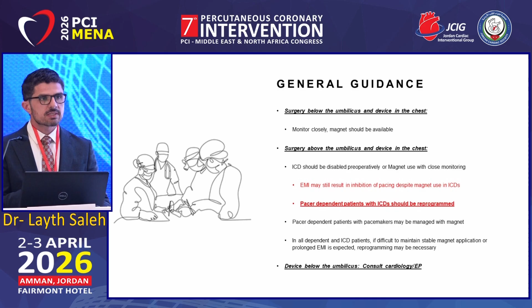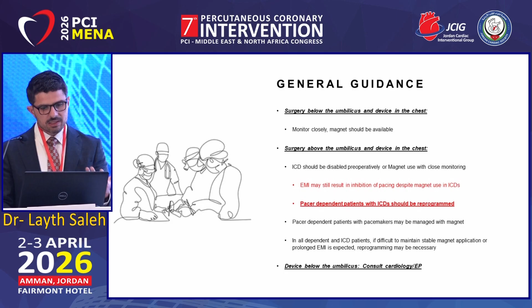Meaning, if you have an ICD with no dependency, then the only thing that we need to disable is the ICD function, which is the magnet. If you have a patient that has a pacemaker and they're dependent on the pacemaker, the magnet will actually cause asynchronous pacing. So these also should be treated with the magnet throughout the procedure. And then we have basically all patients with device below the umbilicus in the abdomen. It's ideal that you consult with a cardiologist before proceeding with the surgery. I'm going to talk about this from the EMI risk in a little bit, which is maybe a little simpler to discuss.